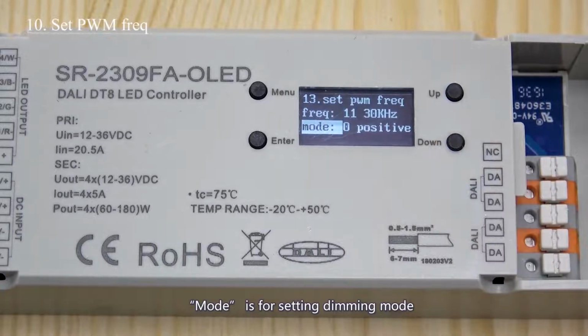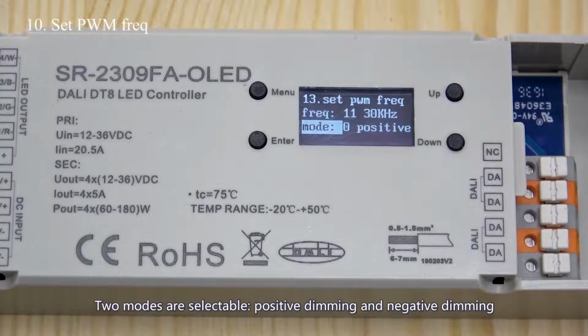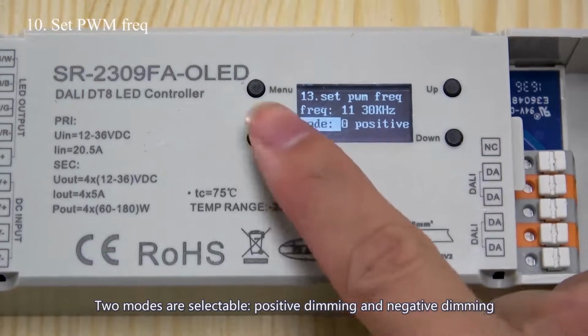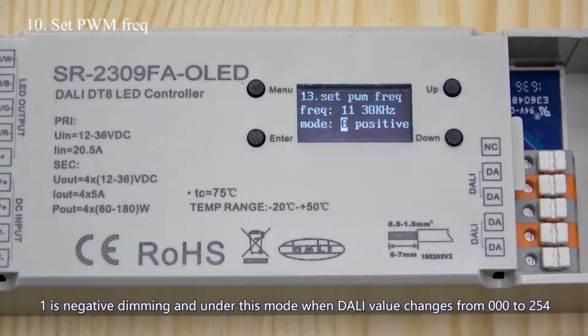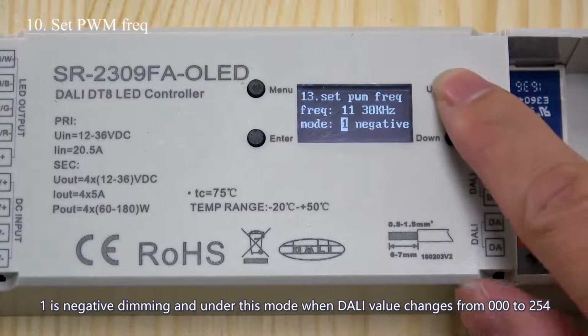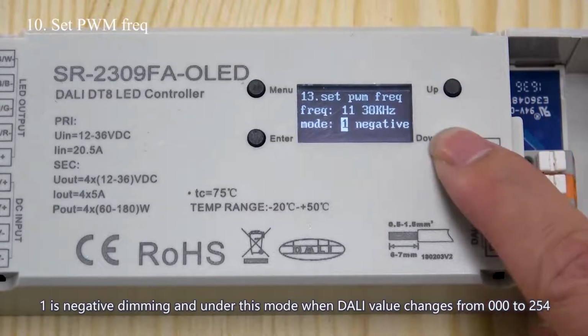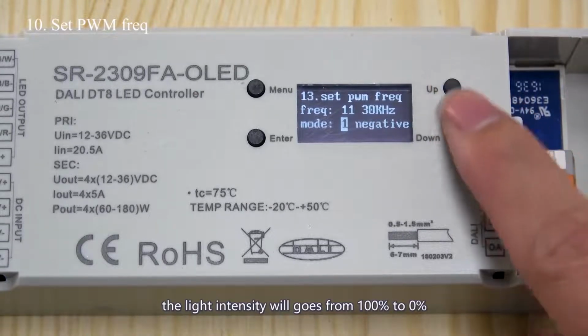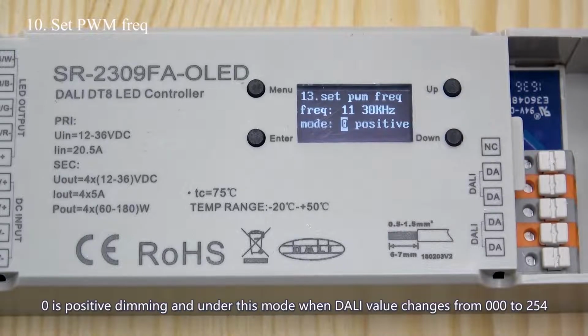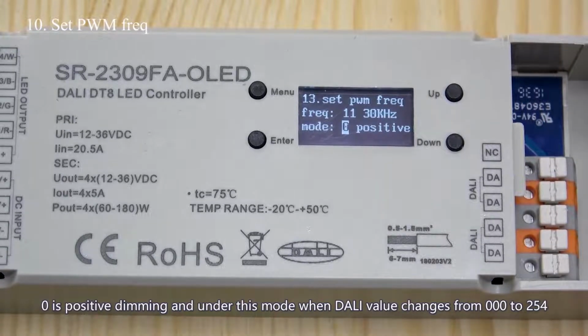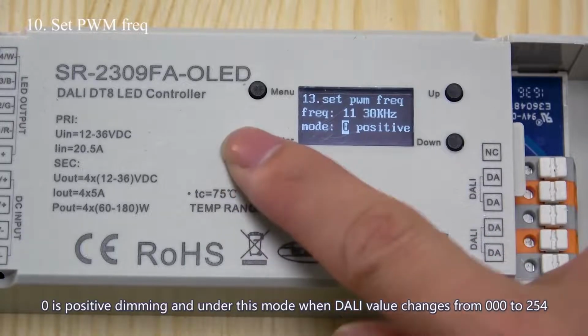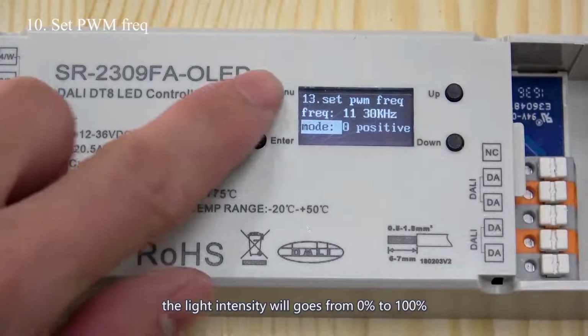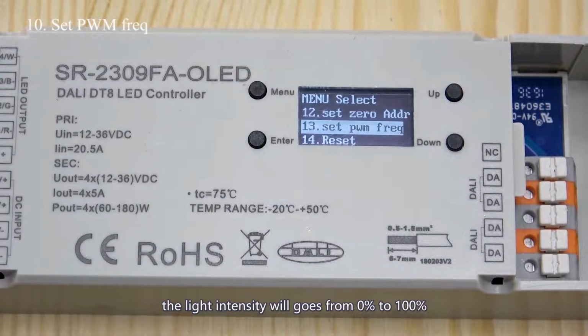Mode is for setting dimming mode. Two modes are selectable, positive dimming and negative dimming. One is negative dimming, and under this mode when DALI value changes from 000 to 254, the light intensity will go from 100% to 0%. 0 is positive dimming, and under this mode when DALI value changes from 000 to 254, the light intensity will go from 0% to 100%.